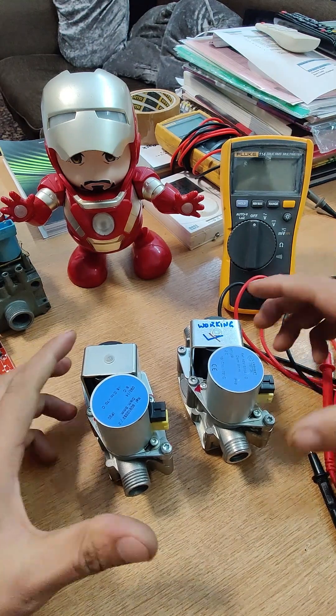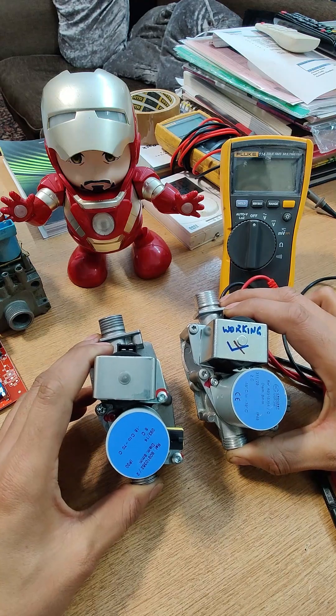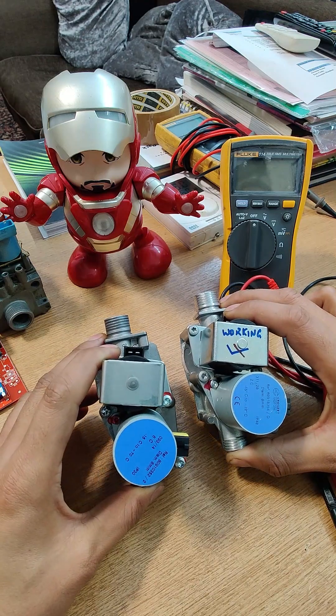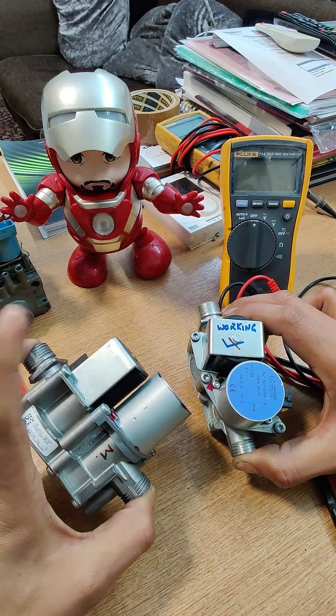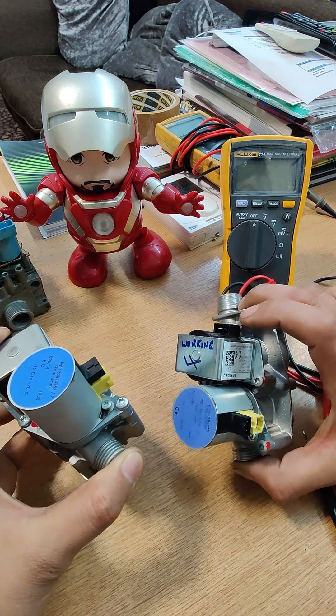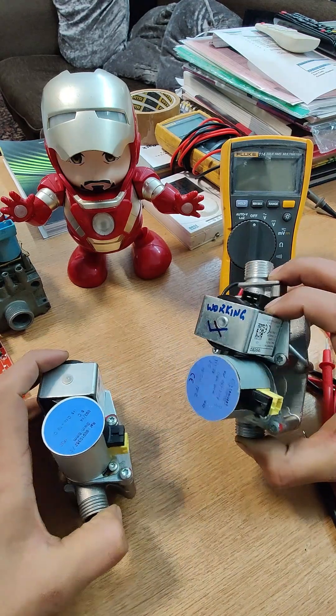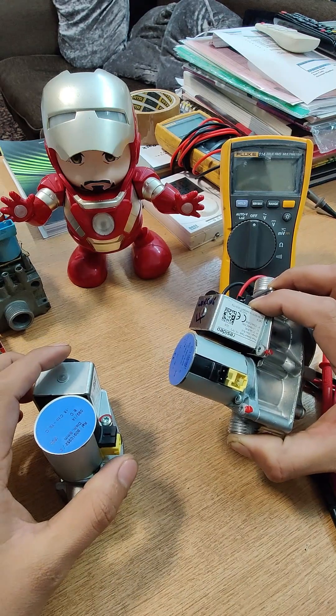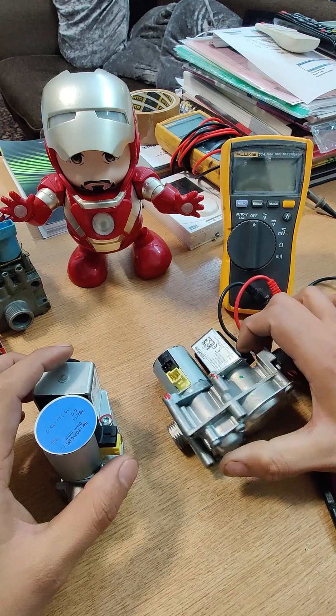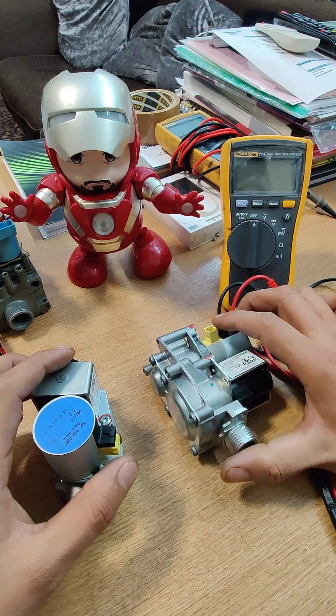Today I've got two gas valves in front of me here. They're both out of a Vaillant Ecotec Plus model. We have a perfectly fine working gas valve and then we have a faulty gas valve. The fault code showing on the faulty one was F26, which is very specific to the stepper motor section of this gas valve.